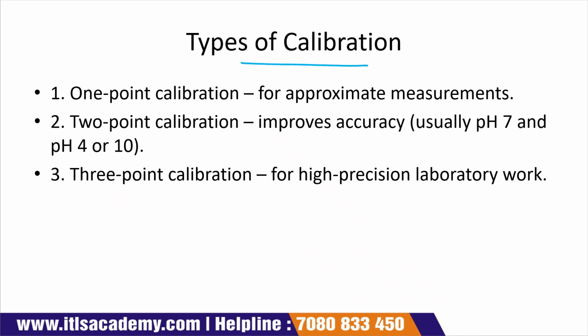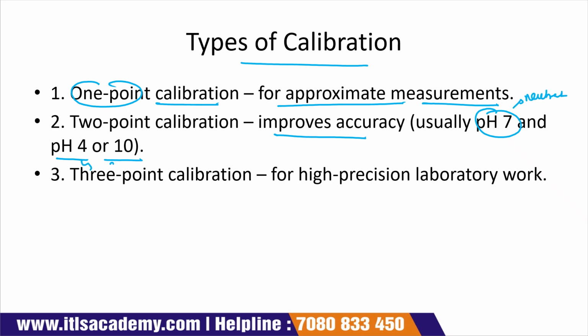Types of calibration. We can calibrate it by using three types. The first one is 1 point calibration, for approximate measurement. When we do a 1 point calibration, it will not give an accurate result, but it gives an approximate measurement. Next is 2 point calibration, which improves the accuracy. Here we use two types of buffer, that is pH 7, and either pH 4 or pH 10. pH 7 is for the neutral, and pH 4 or pH 10 is for acidic or basic. The 3 point calibration is the most accurate type of calibration because it gives high precision for laboratory work.